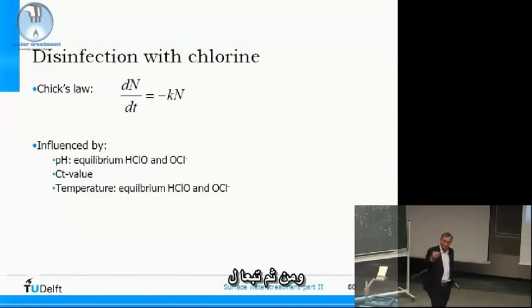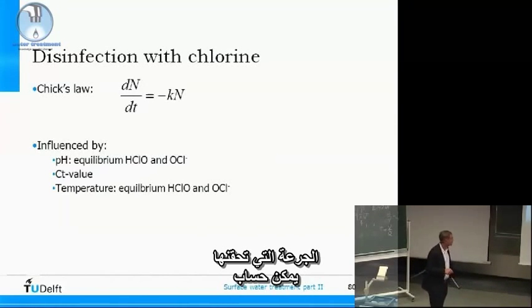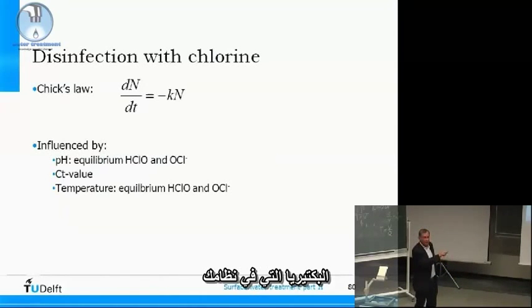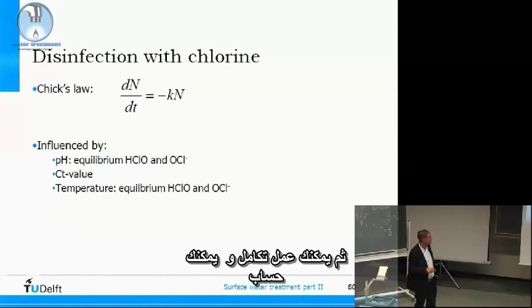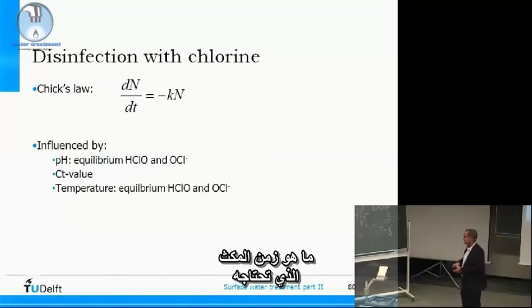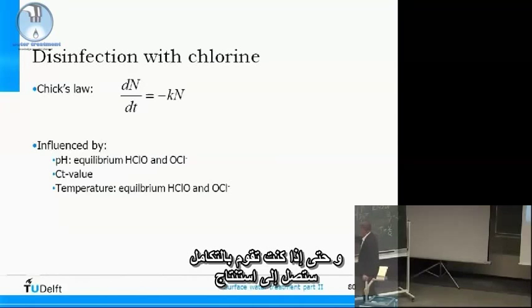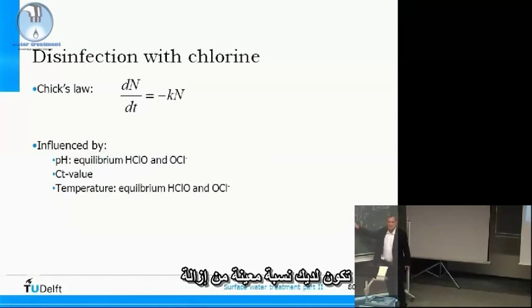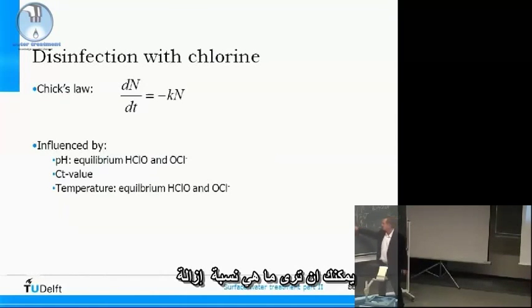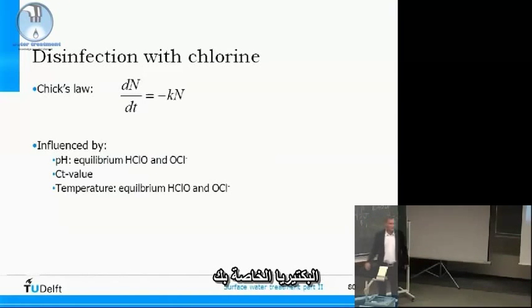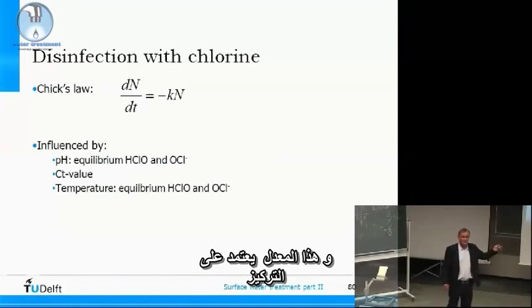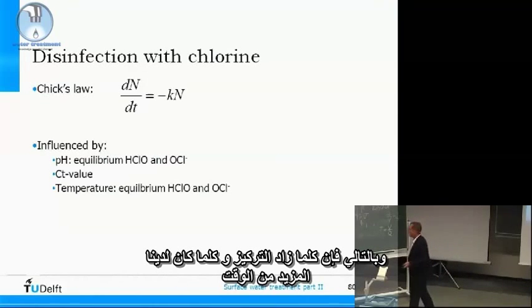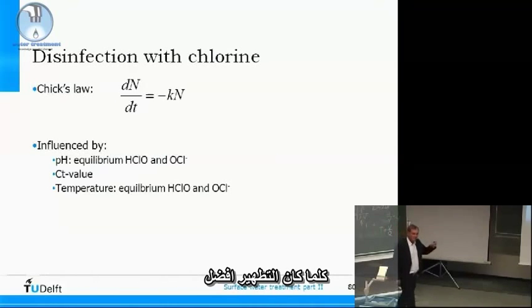Depending on the dose you give, you can calculate the removal of bacteria in your system. You can integrate over time to calculate the residence time needed. When it is plug flow, you get a system where a certain rate of removal and a certain residence time tell you the removal of bacteria. This rate depends on concentration: the more concentration you have and the more time you have, the better the disinfection.